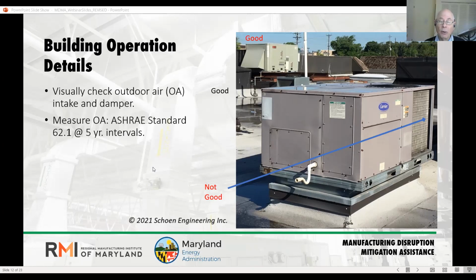This was a facility I was called into because people were complaining of, guess what? Stuffy air and odors. Okay. So we went up on the roof and found, well, no wonder. This unit that was in there for several years never had outdoor air put on it. So you can't assume from drawings, you can't assume even sometimes from balancing reports and even from an inspector's seal, because this was in one of our very carefully regulated counties in Maryland. They missed it too. In the background, you see a system that has, up on that pedestal in the top left of the photo, an outdoor air hood installed. That's what you want to have.